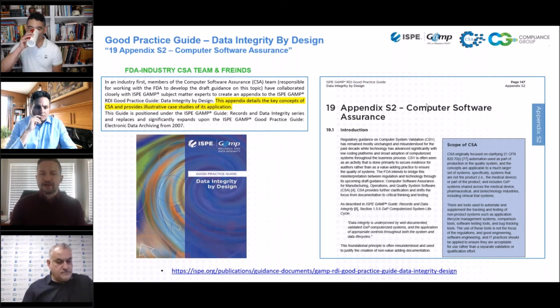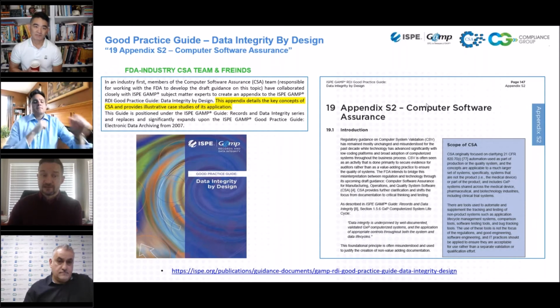This could be a separate data integrity assessment, or you could do this within the requirements assessment. All along, what we've talked about is that when you're looking at your requirements, you're assessing them for the potential to impact patient safety, product quality, and data integrity. When you're doing that data integrity exercise, I say it all the time, data itself is dumb. It's meaningless until you map it to a function. For me, at most, it's an indirect impact. But when you map it to that function and how that data is getting used, and you can do this during the assessment, that's when it has risk.